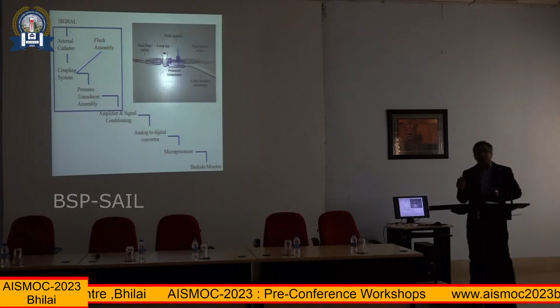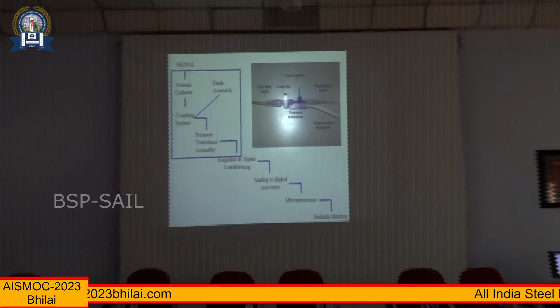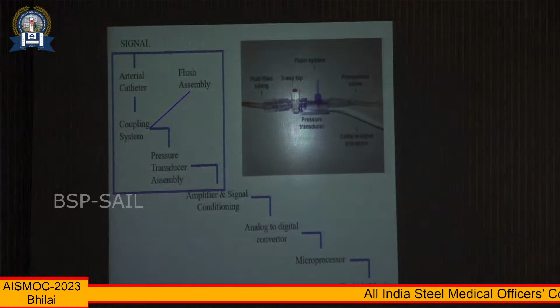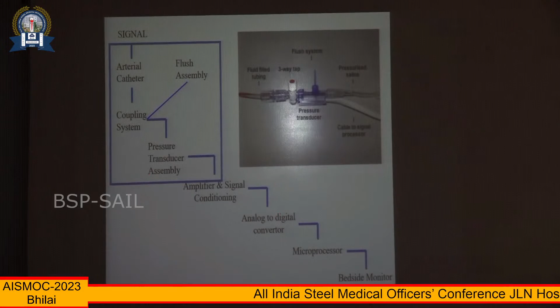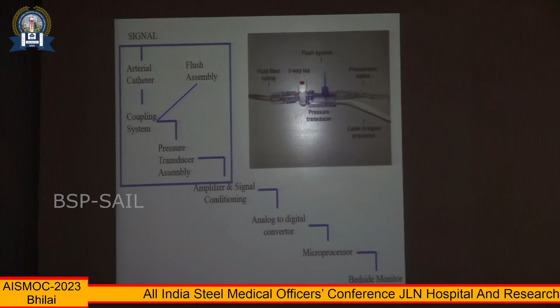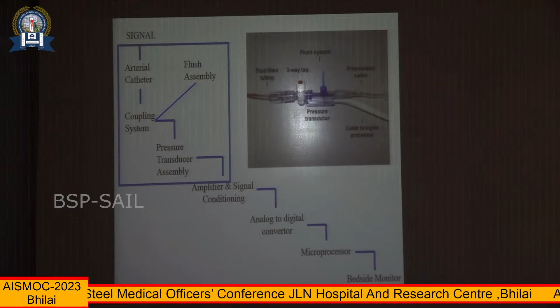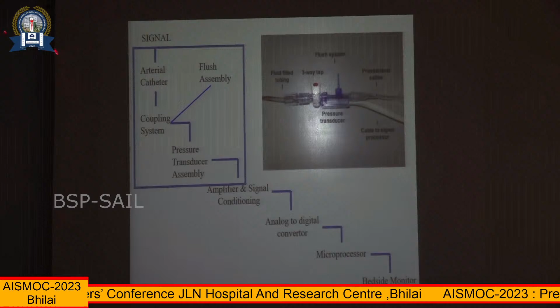Okay, so how does the arterial pressure trace or arterial pressure system work? You can see that you have a catheter in the artery. Then there is a coupling system attached to a flushing system, because we don't want the catheter to get blocked. Then you have a pressure transducer, which is a device that changes the mechanical signal into an electrical signal. Then you have a signal conditioner and amplifier, the analog-to-digital converter that converts the signal to a digital signal, and of course the microprocessor and the monitor.